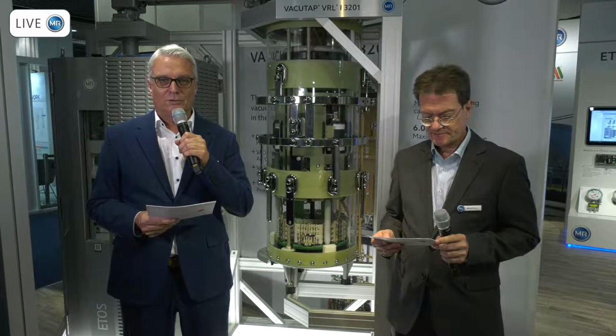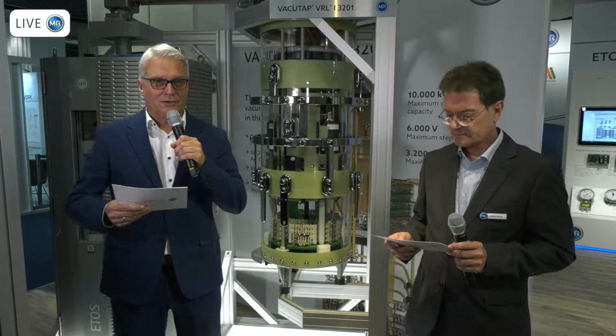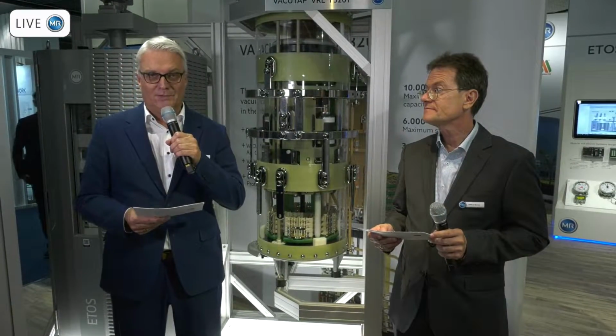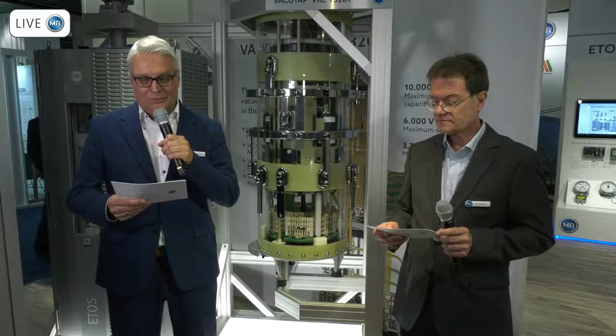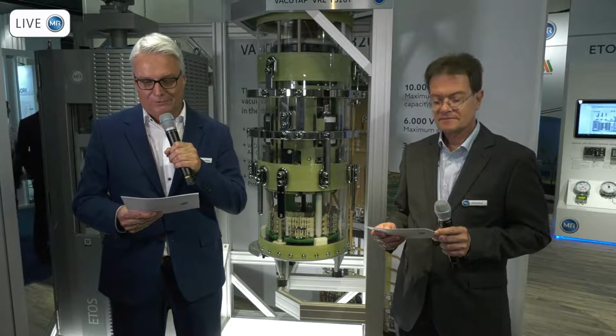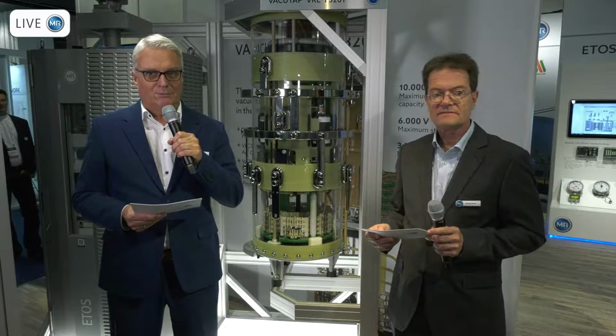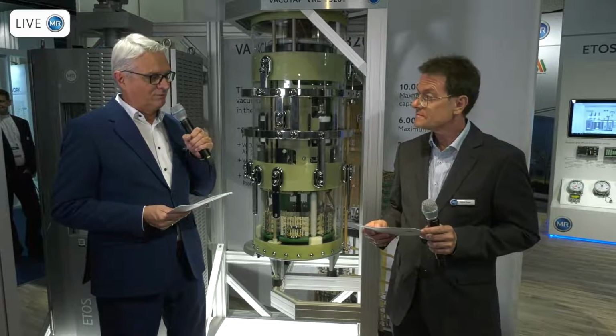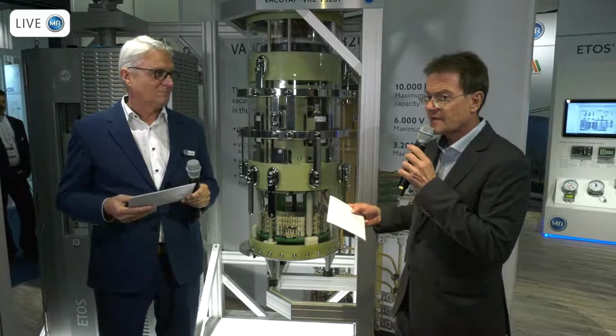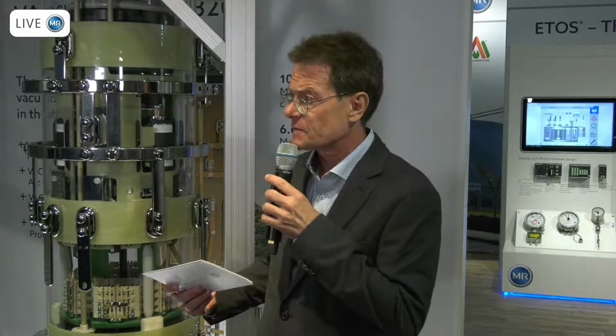We had technical sessions about the VacuTap VRL so far with Jürgen Schwarz, and we want to go a bit deeper into one application. We have talked already about phase-shifting transformers. There's quite a number of new units being installed in Europe, and we see upcoming installations in 2023 and 2024. When we talk about the VRL and other components MR produces, what is special for them when using it in phase-shifting transformers? Phase-shifting transformers have double the amount of tap changers in the design compared with a normal grid coupling transformer. They are used for continuous load flow control in the grid, and therefore the tap changer is permanently used for active load flow control, and therefore it has a very high switching frequency.